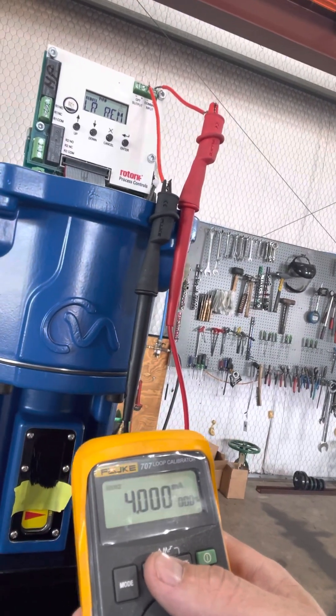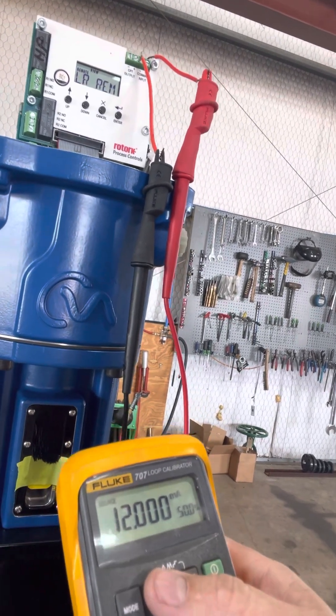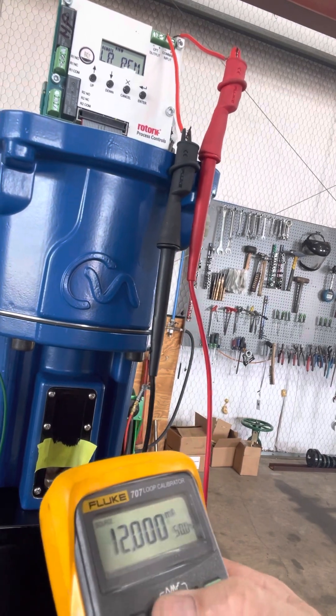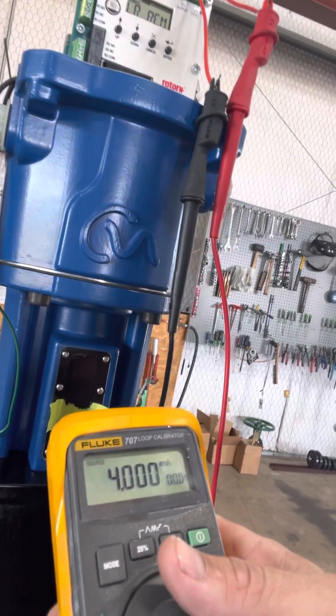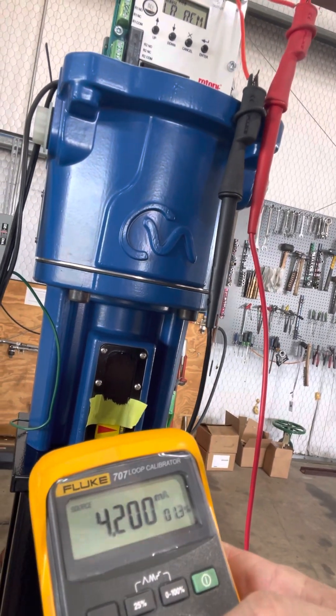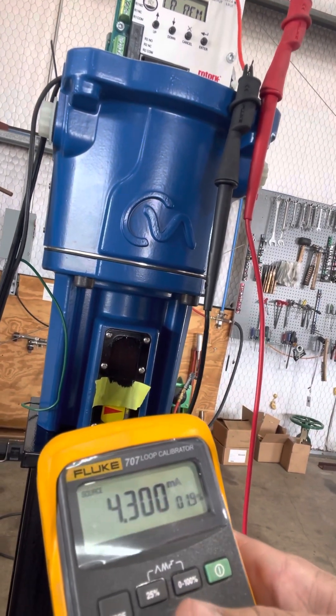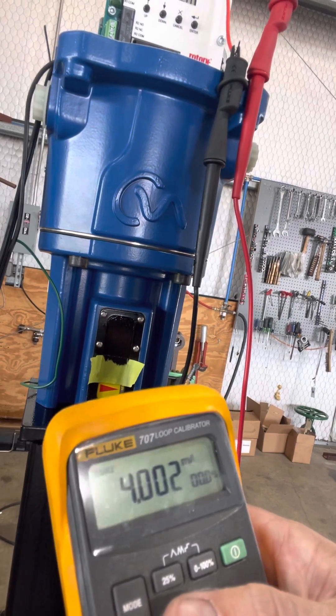This gives a 4 to 20 signal. 25 percent, 50 percent, 75. Now we're just going to go back to 4. And then you can tell just by barely moving it that the actuator is moving. Well, I can tell because I can hear it. I'm not sure if y'all can hear it. Even at 4.1 it moves.